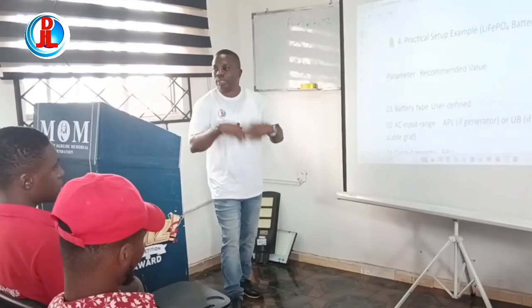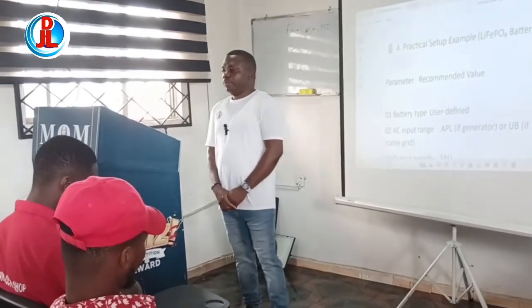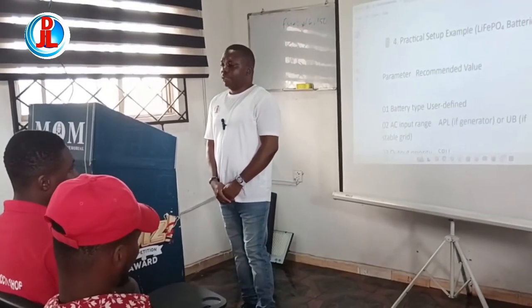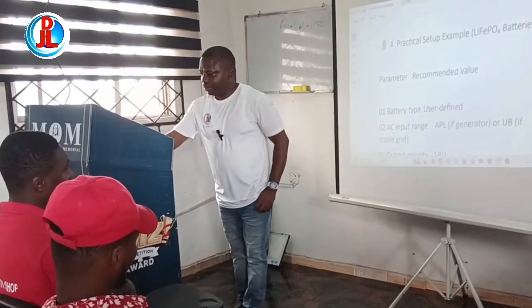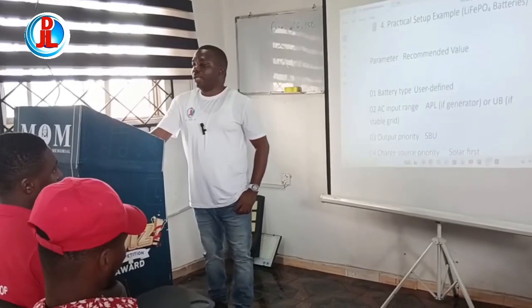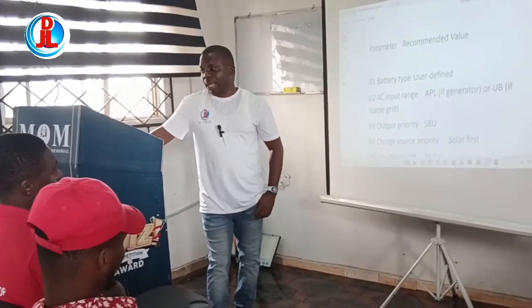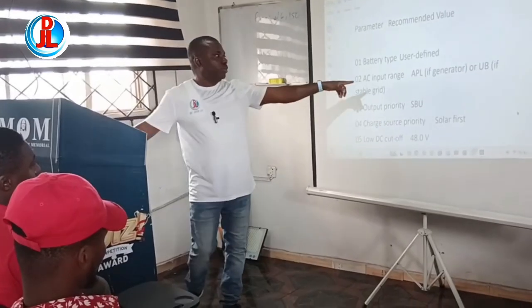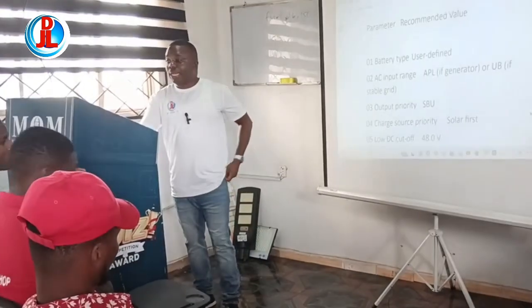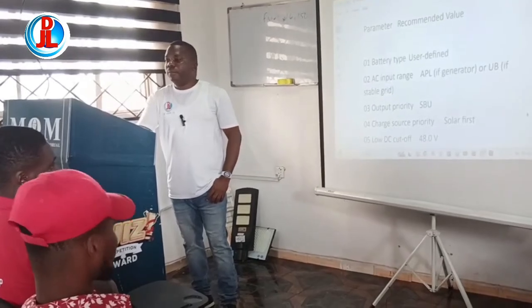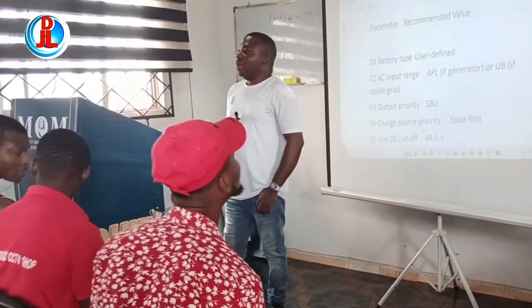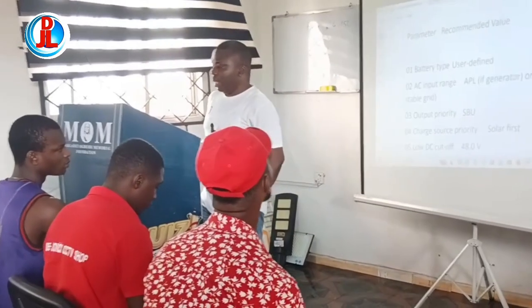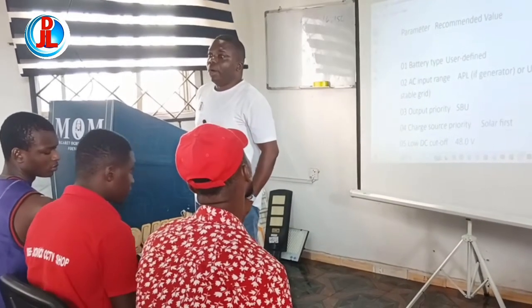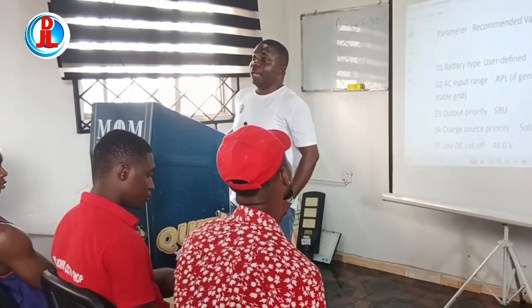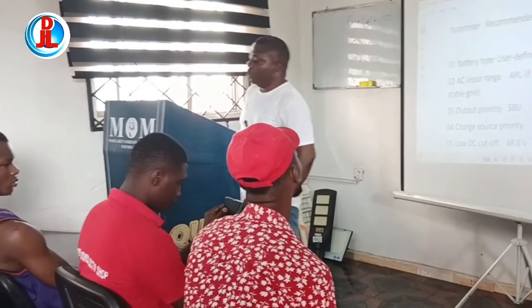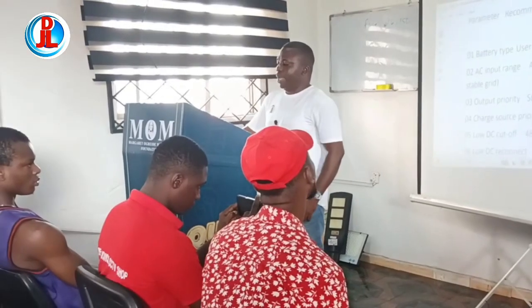Practical setup example. Let's use a lithium battery. Parameter recommended. Battery type user-defined. So on that battery type, 01, you set it as lithium. You understand? 02, APL if generator, or UB if stable grid. If you are in a place where the electricity is stable, you can use UB. But if the electricity is not stable, use APL. In most cases, the electricity is not stable. So please change it to APL.